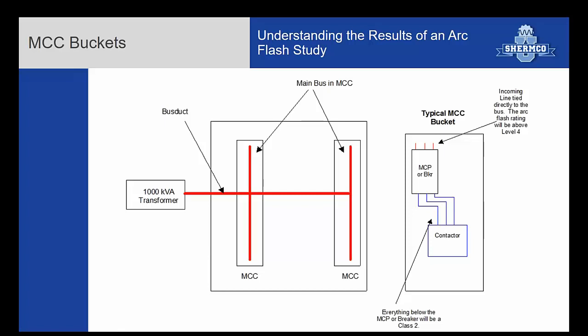However, if you're just working inside the bucket and you're not getting on these line side stabs, the incident energy was level 2. So if people are troubleshooting overloads or electricians are troubleshooting starters, they're not physically racking them on or off the breaker, off the MCC, then level 2 is enough. But in this case, every bucket was labeled dangerous. It's kind of more about understanding what task you are doing.